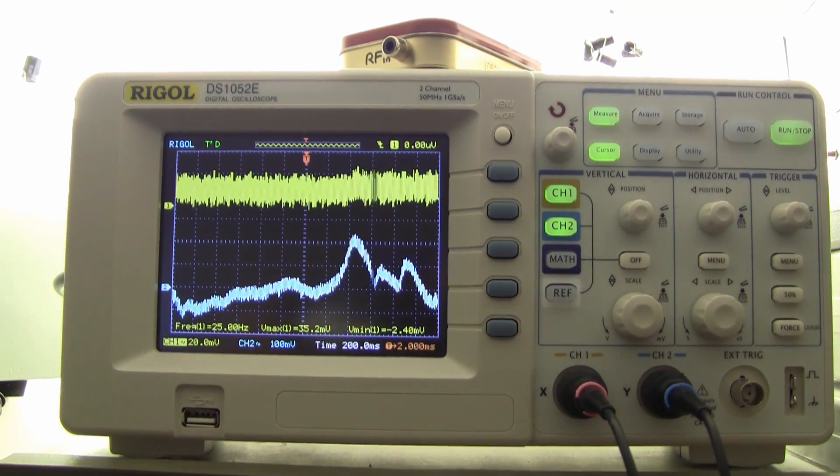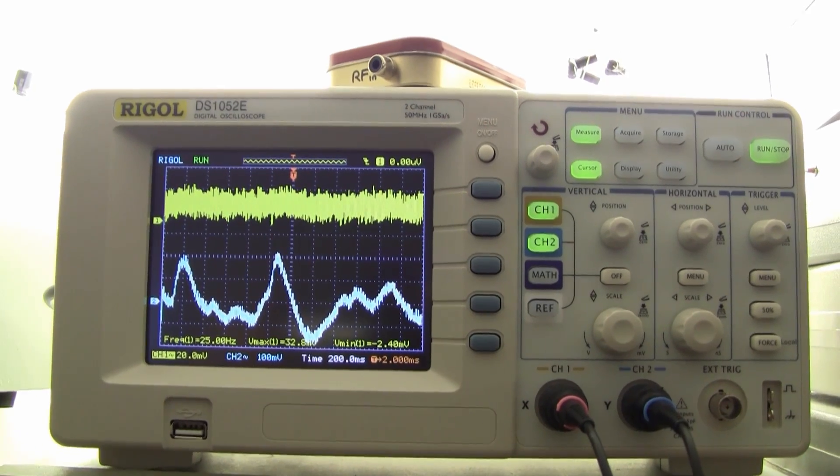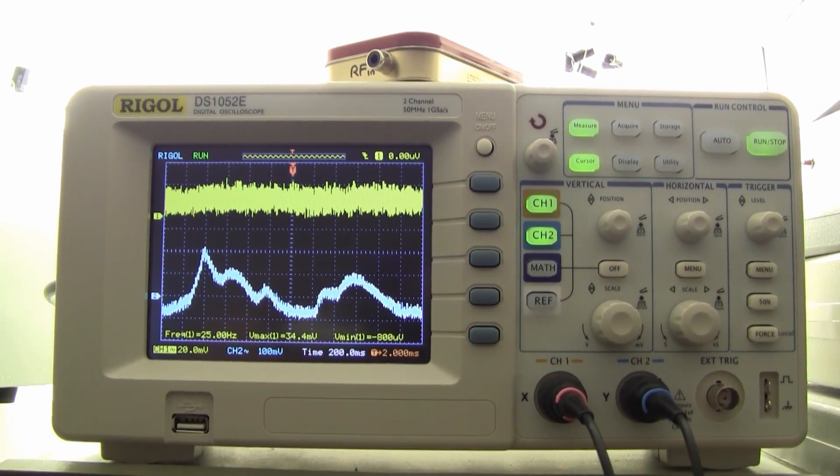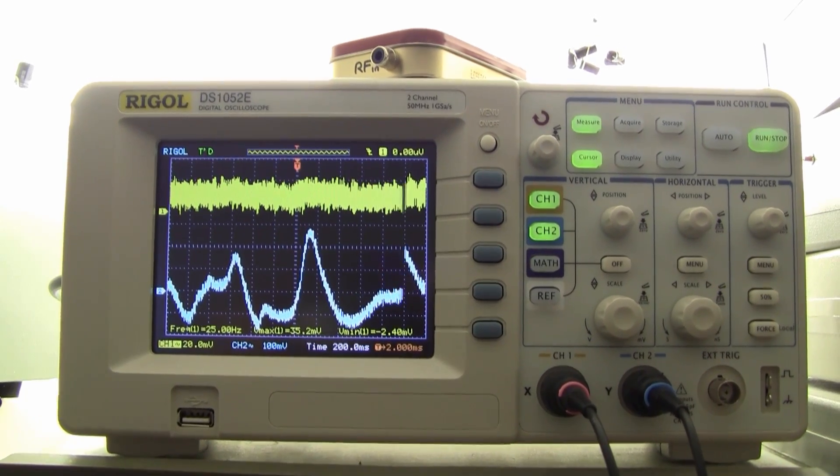And how it really works, we can see up here on the oscilloscope. The top trace, the yellow trace, is the raw signal out of the ion chamber. You can see it's pretty noisy. The bottom blue trace is low-pass filtered and then amplified quite significantly, only at the low frequencies.